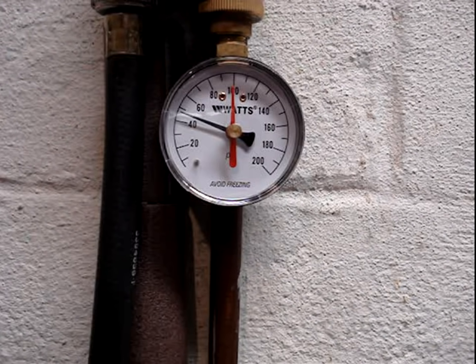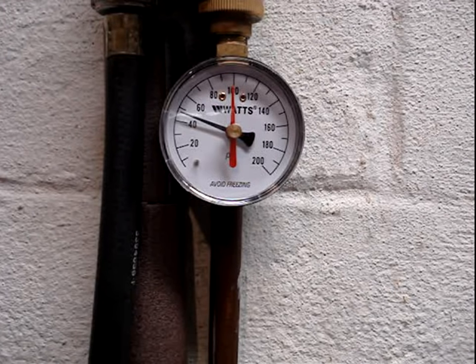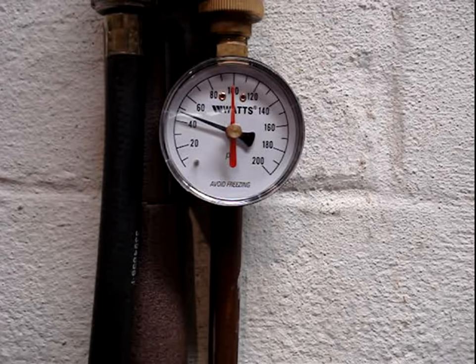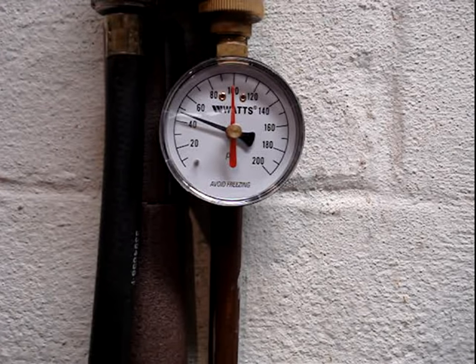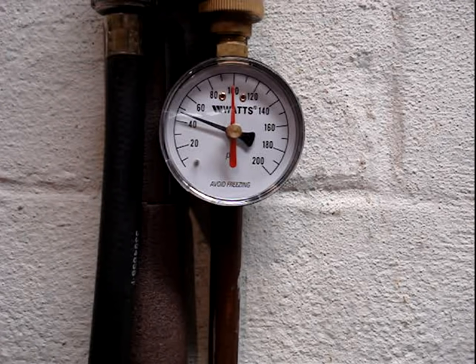The normal range for water pressure should be between 40 and 80 psi. Most communities have adopted plumbing codes that require a pressure reducing valve be installed if the municipal water supply pressure is greater than 80 pounds. This is an open system with a pressure reducing valve that has a bypass.